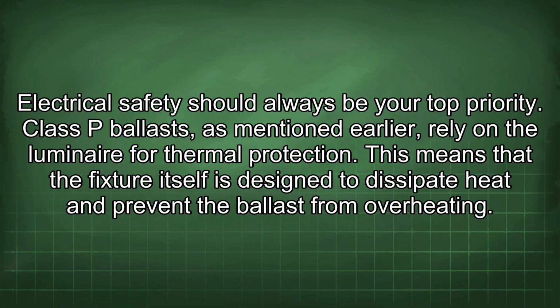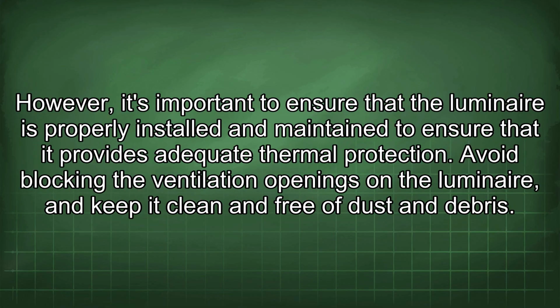Class P ballasts, as mentioned earlier, rely on the luminaire for thermal protection. This means that the fixture itself is designed to dissipate heat and prevent the ballast from overheating. However, it's important to ensure that the luminaire is properly installed and maintained to ensure that it provides adequate thermal protection. Avoid blocking the ventilation openings in the luminaire, and keep it clean and free of dust and debris.